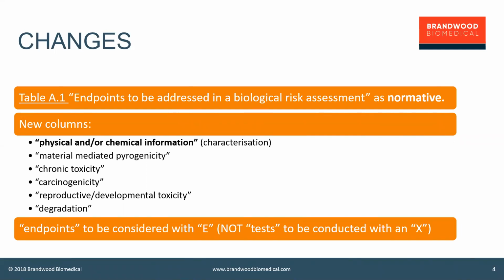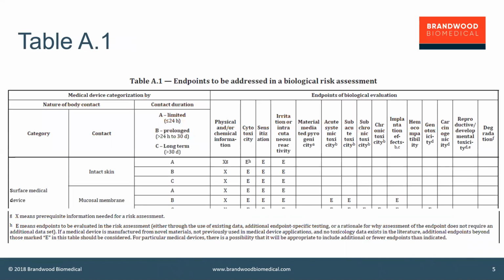Let me now show you a cut from the Table A.1. and you can see that physical and chemical information is in fact the first column in the endpoints after contact duration on this table. And there are X's for every contact duration and every body contact type. So you need to do physical and chemical information evaluation for every device you're evaluating. You'll also notice that material-mediated pyrogenicity is present here, and I'll speak to that specifically in a little while.